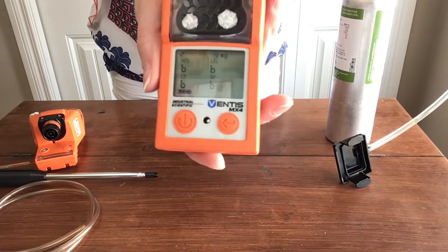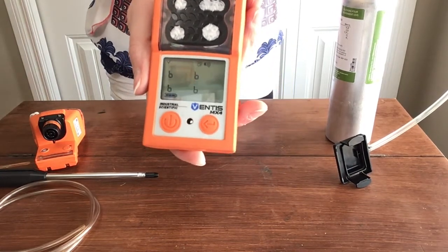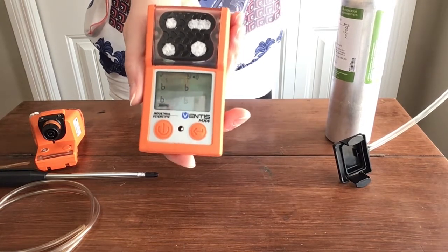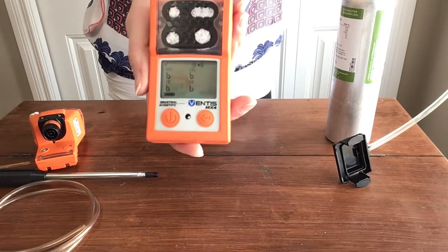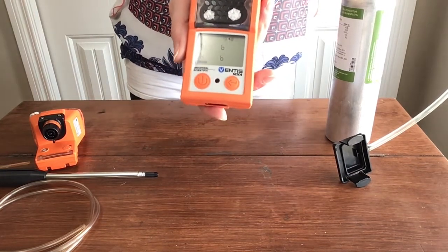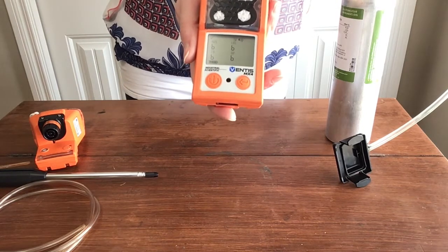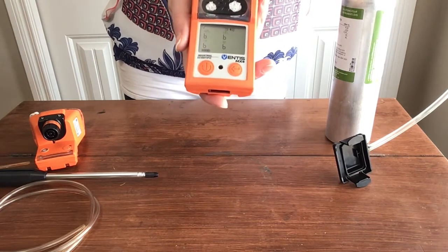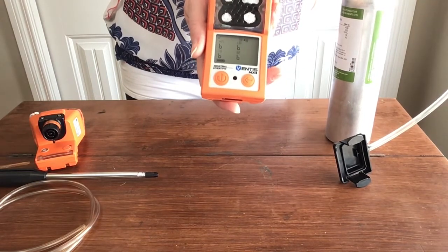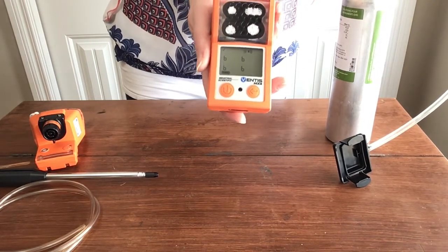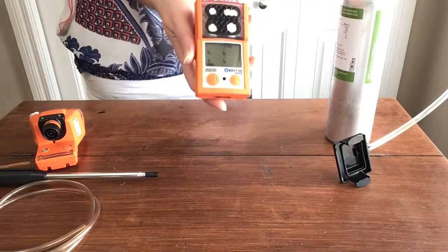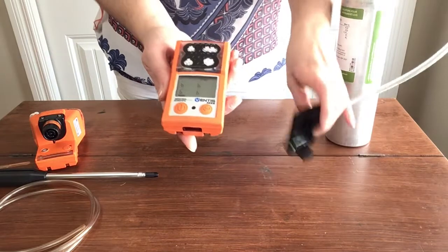Now, that is your monthly calibration. We still have to do a bump test before we use it to clear these B's here. Okay? So a bump test is essentially a quick and dirty calibration. Okay? It doesn't take the same amount of time that a calibration takes. It goes through very quickly to make sure that the gases can be sensed, that they're within a range, and that the alarms are working. Okay? It doesn't check any of the internals necessarily the same way that the calibration does.